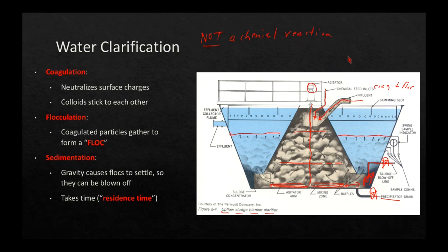Okay, the chemicals that we are adding do not react with the dissolved particles, or not dissolved particles. I've got to stop saying that. Suspended particles. There's no reaction going on here. All there is is a stripping away of electric charges and sort of a bridging together of the tiny little flocs to form large flocs that fall out of suspension. So the floc that has fallen out of suspension is called sludge, and that's actually a really good thing, because what's going to happen is it's going to filter the water.